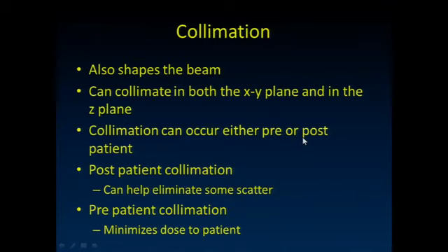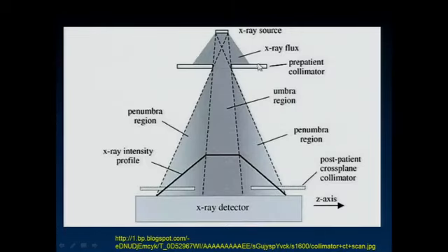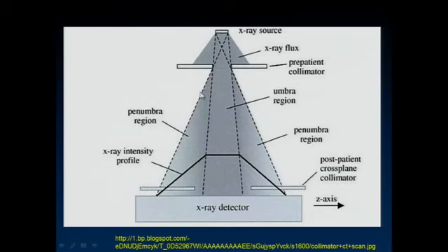We also do collimation, just like in fluoroscopy. You can collimate in either the z-axis or the x-y axis, pre- or post-patient. Post-patient collimation helps eliminate some scatter hitting the detector, which is important in certain types of imaging. Pre-patient collimation reduces dose to the patient. We'd like to bring pre-patient collimators in so that our x-ray beam is no wider than the detectors—it makes no sense to irradiate parts of the patient where that radiation won't strike the detector. Post-patient collimators can also eliminate scattered radiation from outside the primary beam field from striking the detector.